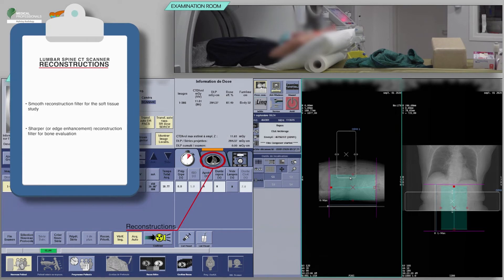For the acquisition of a lumbar spine, you will need at least a smooth reconstruction filter for the soft tissue study and a sharper or edge enhancement reconstruction filter for bone evaluation.